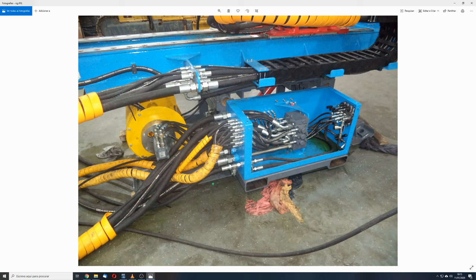So nothing special here. As I said before, this is a core drilling rig, and we'll be checking and adjusting the delta P by activating the drilling head rotation, which is the easiest way because it allows me to work with continuous flow as compared to a cylinder function, for example, in which case the test would be limited in time by the cylinder's travel.